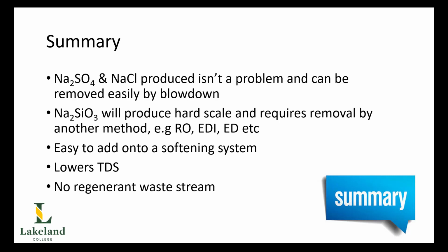The sodium silicate, however, that one's a problem. It will cause hard scale and it does need to be removed before it gets to the boiler. Now, how do you remove it? Well, I mentioned one method, reverse osmosis. There are others, of course, like EDI, electrodeionization, or ED, electrodialysis. There's all sorts of ways it can be addressed.